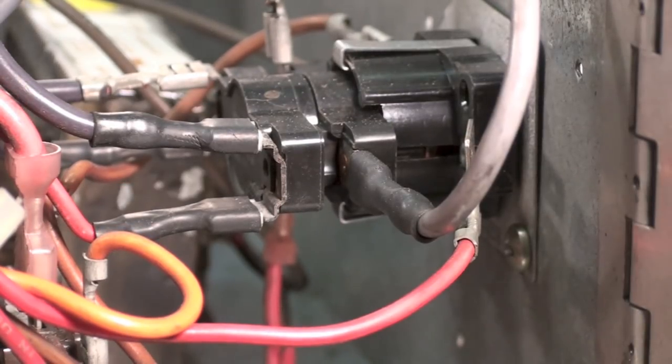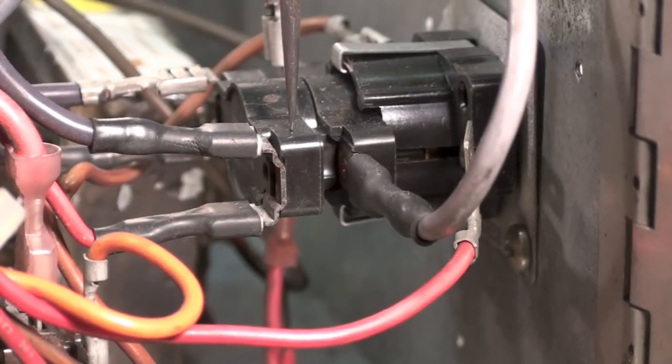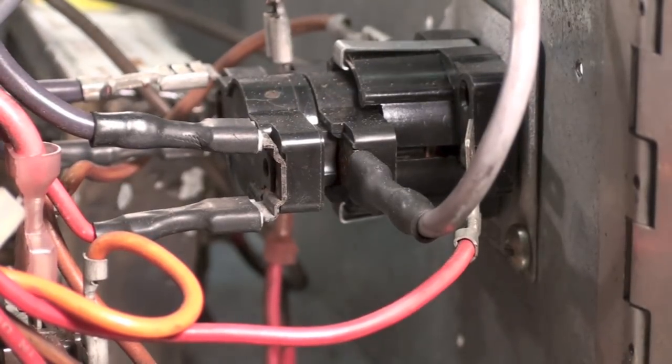The reason they set them up that way is when electric furnaces first came out, the transformers used in most residences—the pole transformers—really were not big enough to have large electric furnaces on them. They would kind of brown out if you turned on all the elements at the same time, so they came up with sequencers. It turns one on and then another one after the transformers had a chance to catch up.